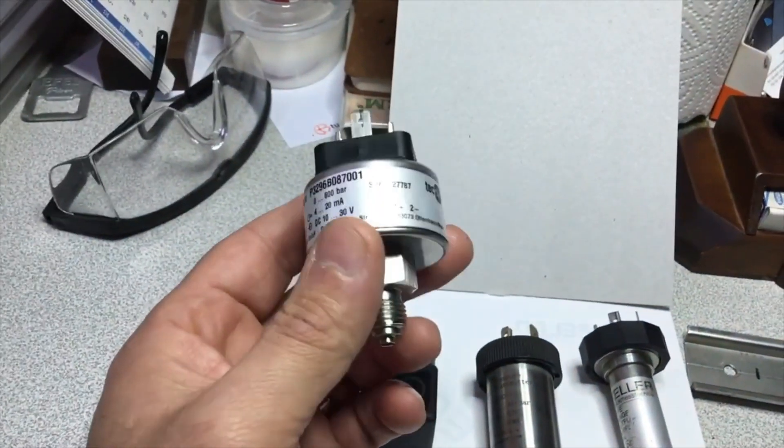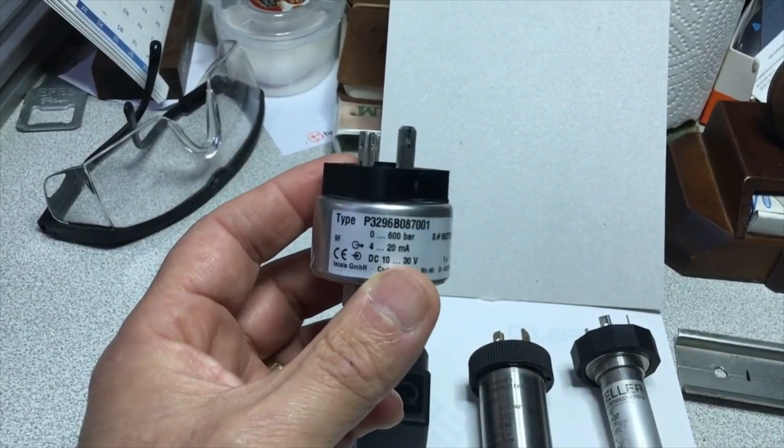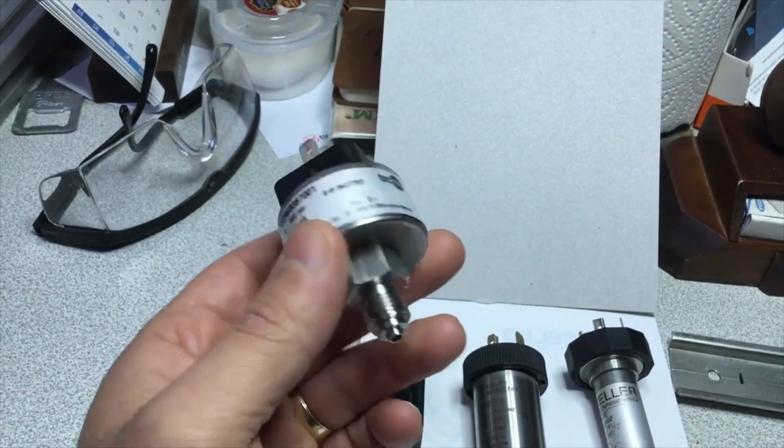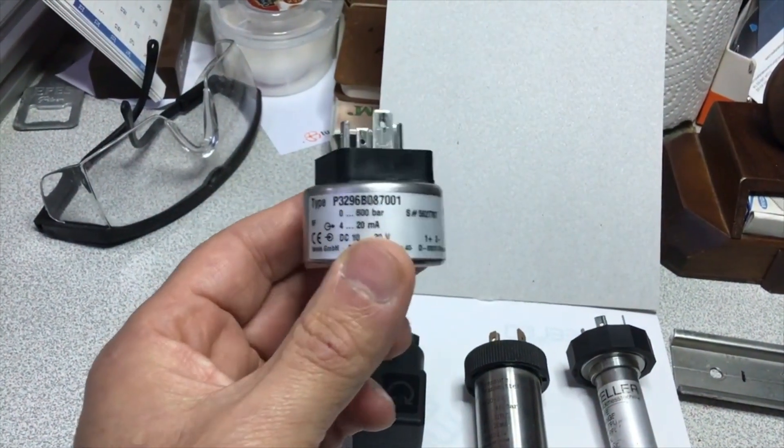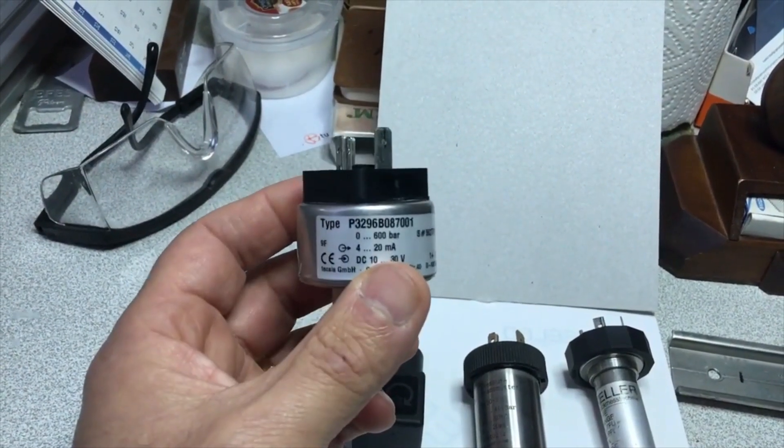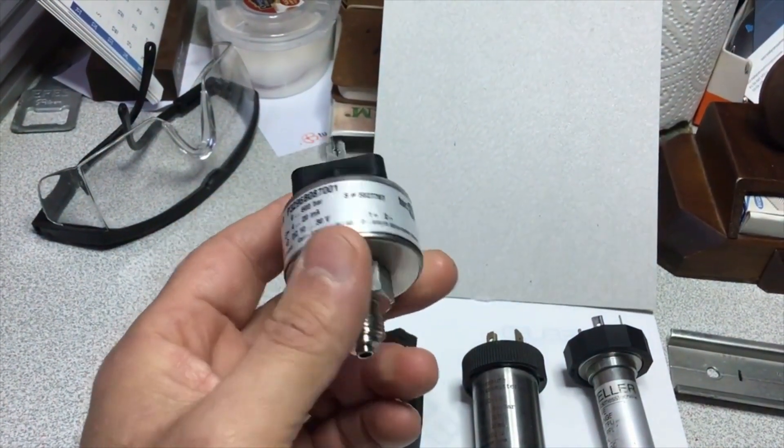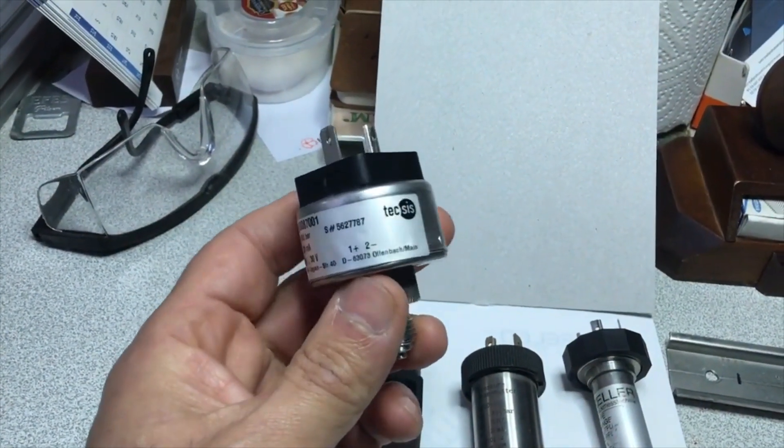We also read the correct values with 0 to 20 milliamperes, that is, independent of the cable length, but when the cable breaks or the sensor fails and cannot output, the system will take it as 0 bar as the controller system pressure, so we get wrong information.